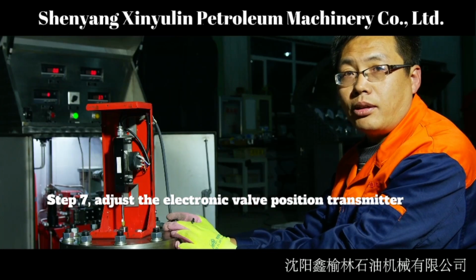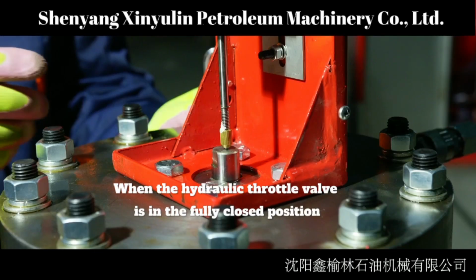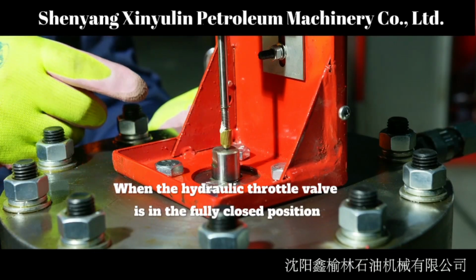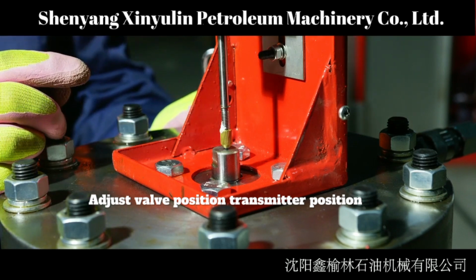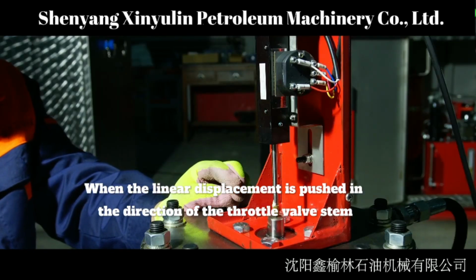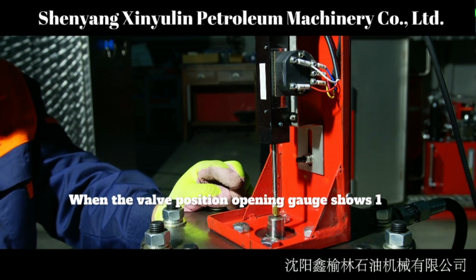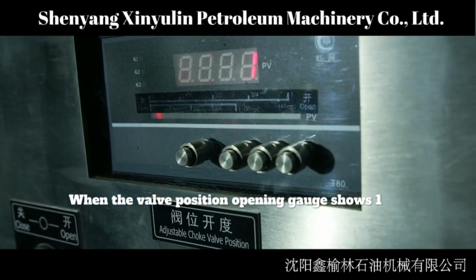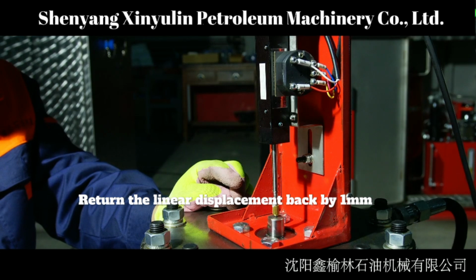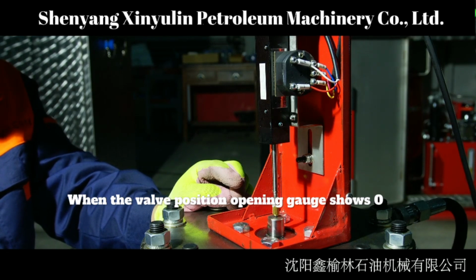Step 7. Adjust the electronic valve position transmitter. When the hydraulic throttle valve is in the fully closed position, adjust the valve position transmitter position. When the linear displacement is pushed in the direction of the throttle valve stem, when the valve position opening gauge shows 1, return the linear displacement back by 1 mm. When the valve position opening gauge shows the set value, tighten the valve position transmitter screws.